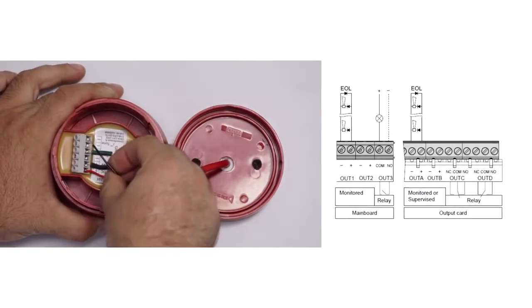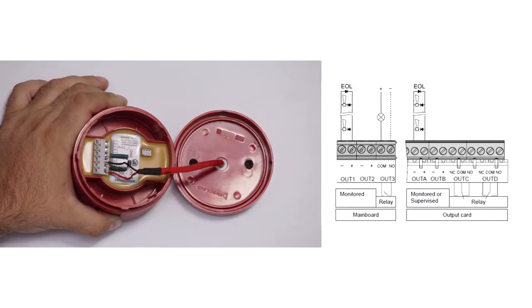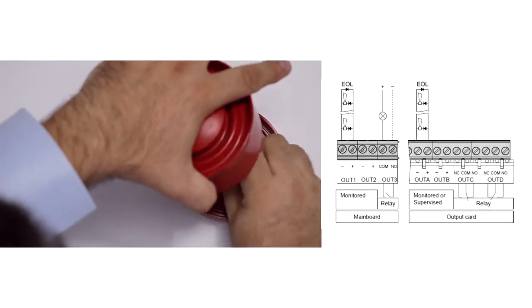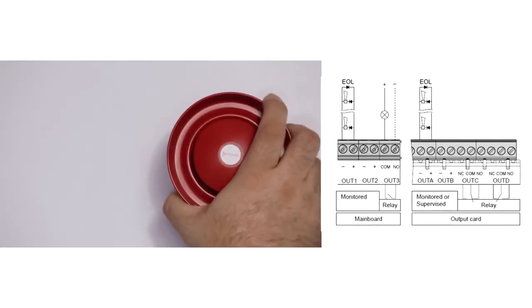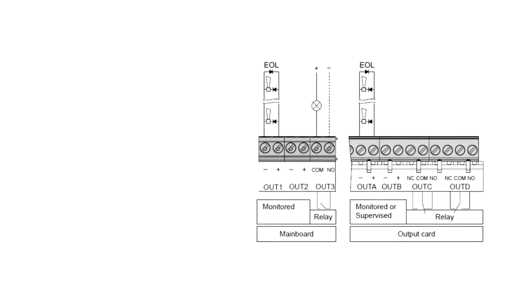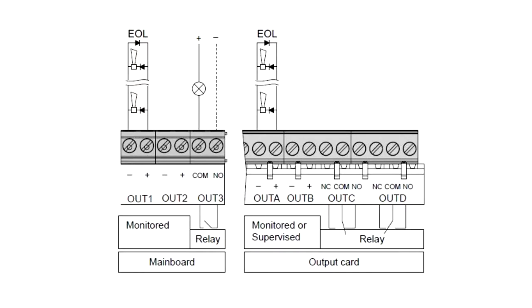Outputs are used to transmit system status information. As a result, 3 different types are available: monitored, supervised, and relay. In our demonstration, we will focus on the monitored mode, where the panel monitors the line in terms of open and short circuits only. To do this, you have to install an end-of-line element at the end of the cable. For monitored output, this is a diode 1N4007. During the inactive status, the panel only measures the diode because of the installed diode in every device. In case the output is triggered, the panel changes the polarity and the devices are activated. The panel provides a maximum current of 0.5 amperes over 24 volts DC for the FC121 and FC122 and 1 ampere for the FC123 and FC124.